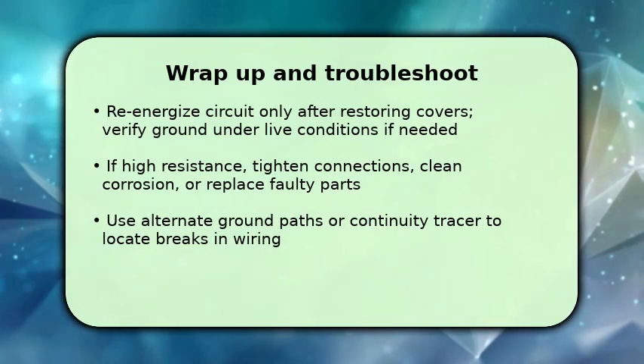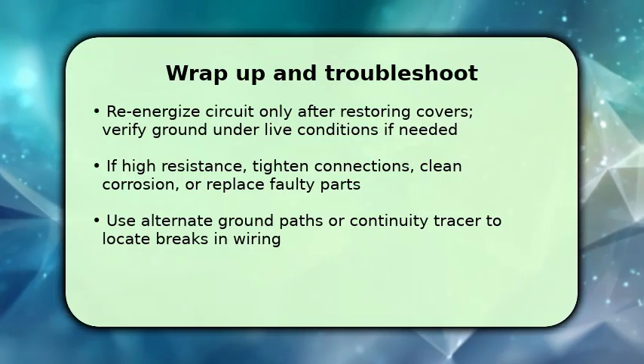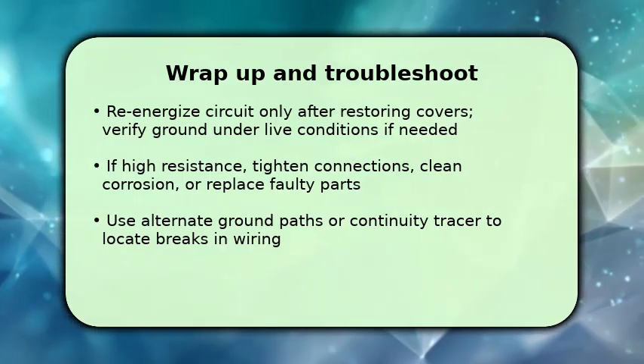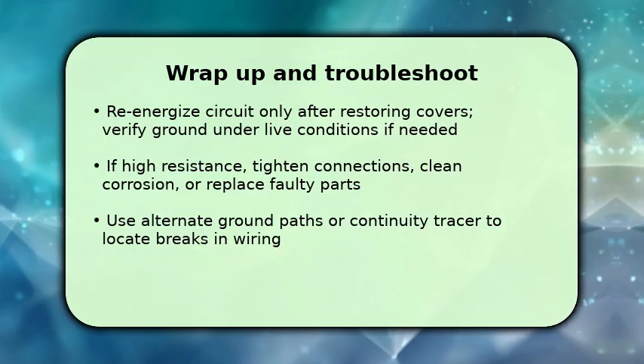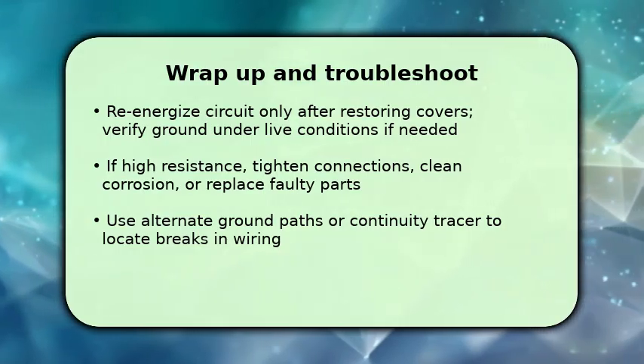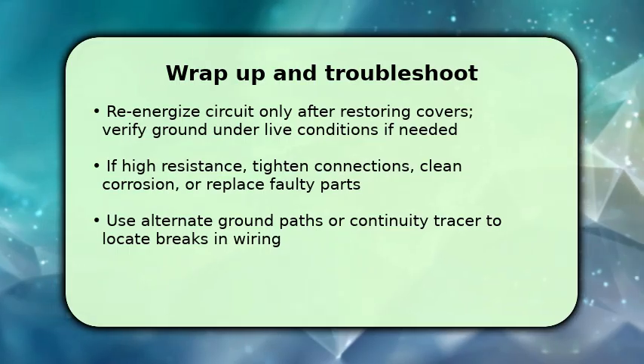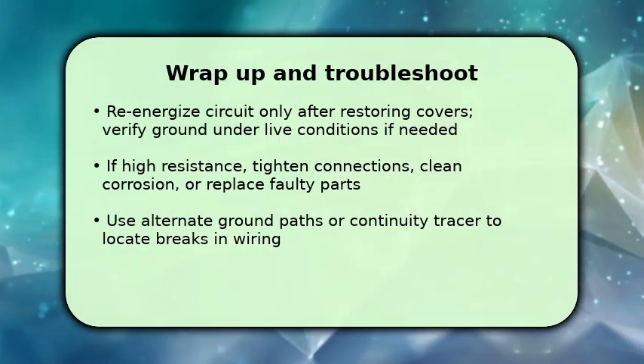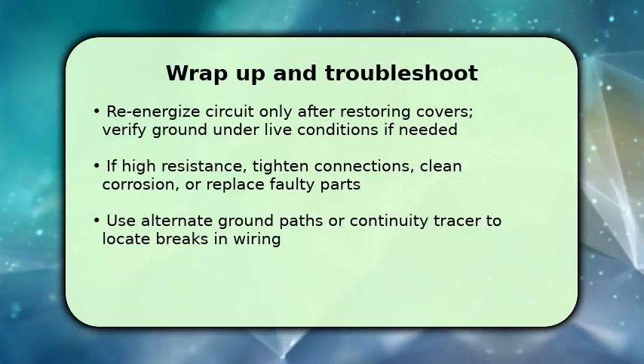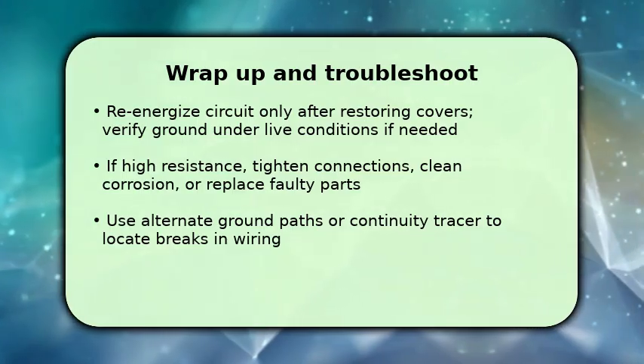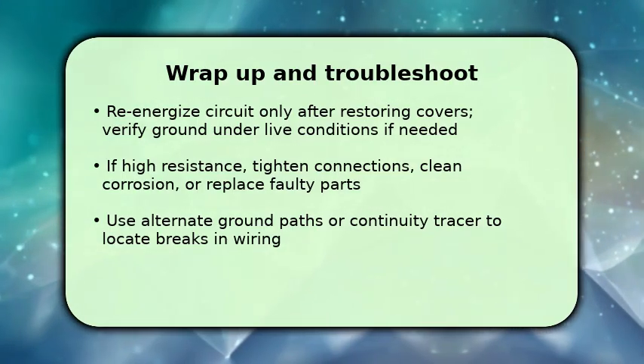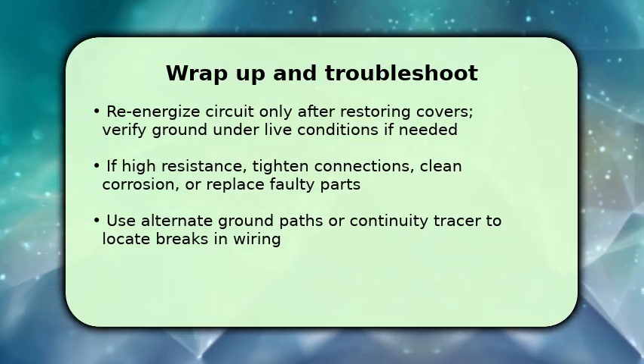If you found high resistance or no continuity, tighten loose ground screws, remove corrosion, or replace damaged wires. Cleaning contact surfaces often fixes the issue. Make sure to retest after each fix. If problems persist, use an alternate ground path or a dedicated continuity tracer to locate breaks inside conduit or cable.